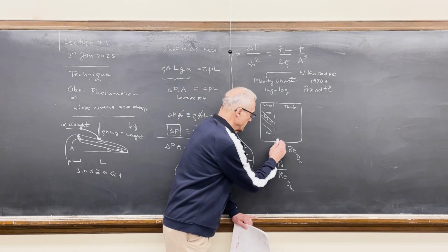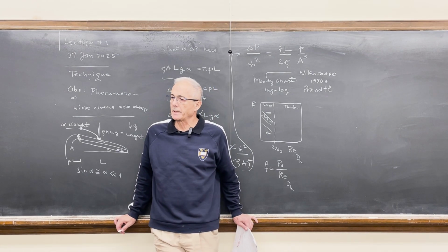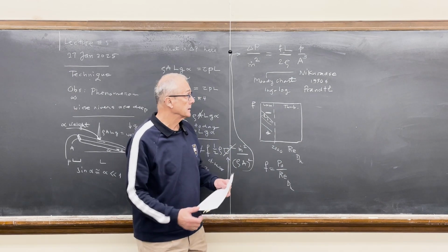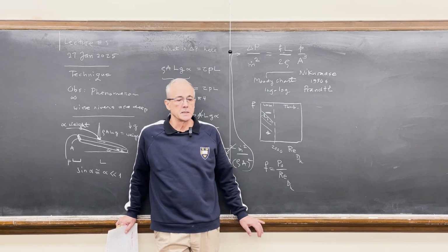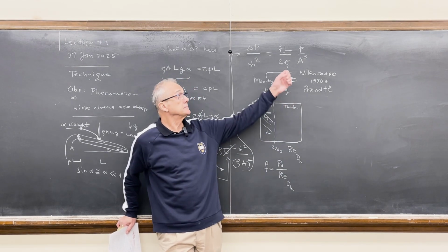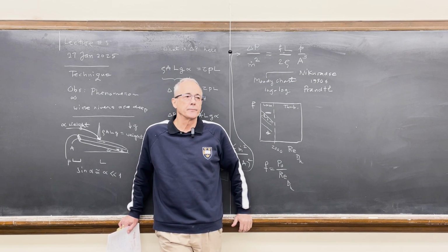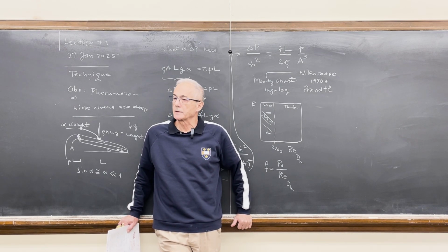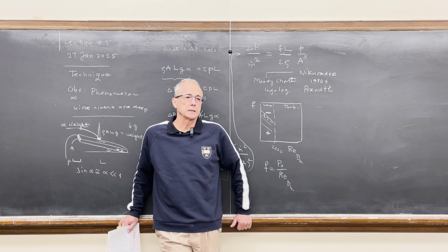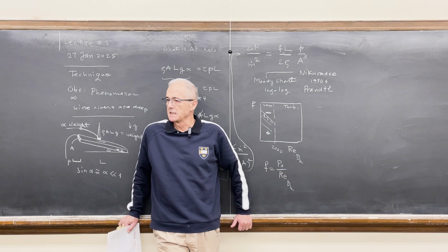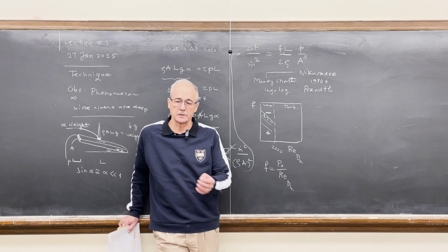On the right-hand side of this so-called transition Reynolds number, you have another bundle of curves, and this is where Nikuradse made himself and the professor and the laboratory famous. Nikuradse, of course, measured the delta P and the mass flow rate squared, but he did it in a multitude of channels, pipes in his case, round pipes, with controlled internal surface roughness.